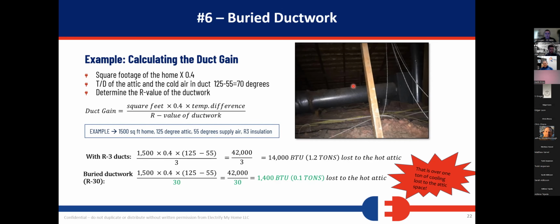So it's not untypical for us to put an 18,000 BTU system in an old 3-ton house if I've insulated the attic well, done some air sealing, and buried the ductwork in insulation. So what happens when I have an 18,000 BTU system versus a 36,000 BTU system? First of all, it costs me less to buy that equipment. I'm now presenting them with a premium solution that I can charge more for. So my profit margin comes up a bit.